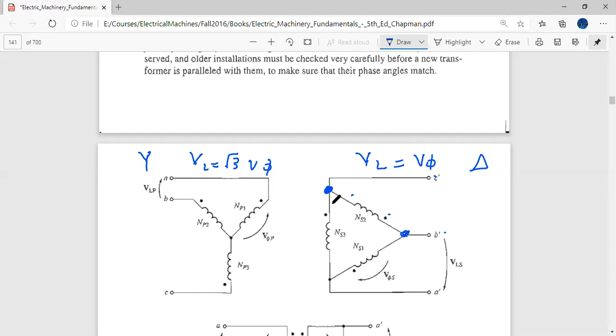So in your household, the connections come through a Y connection. From the transformer also, you get the connections through a Y connection, never a delta connection. So this relationship holds, but for a delta connection, the phase voltage equals the line voltage, because the phase voltage is also measured across one coil, and the line voltage is also...